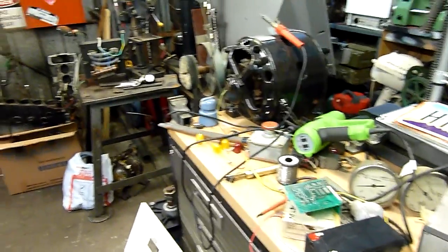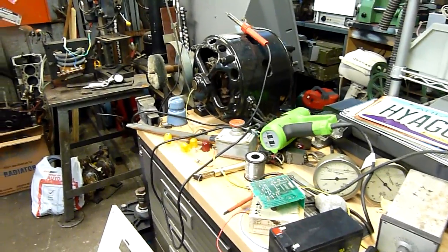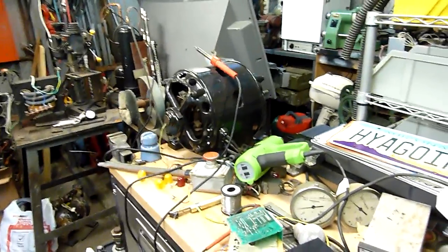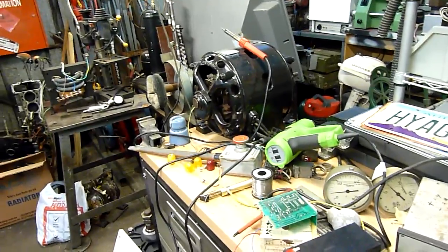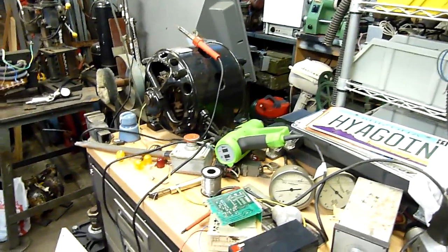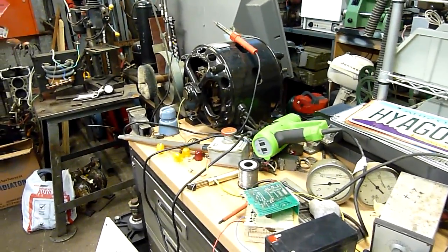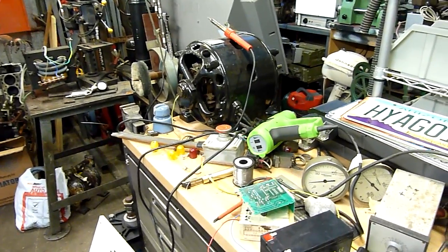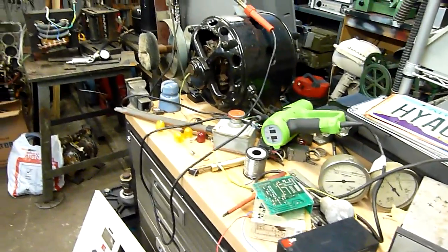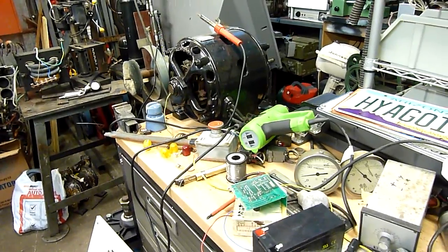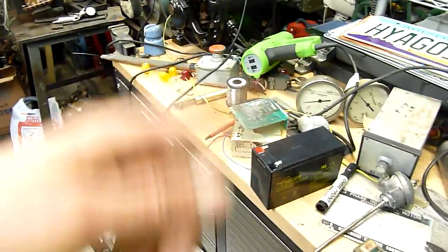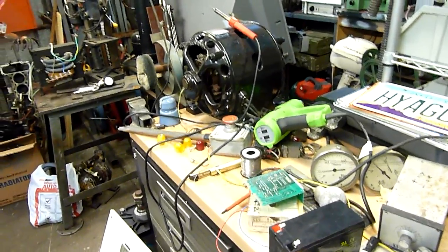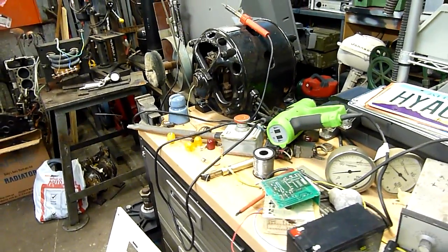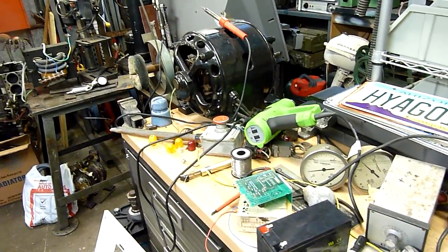Main thing I'm concerned about is this motor is oil cooled, or has an oil to water heat exchanger and everything in it. Likewise, I think a lot of that oil is also lube oil for the bearings, but I'm curious whether it would contain polychlorinated biphenyl. I doubt it, since it shouldn't be in contact with the windings. It wouldn't be inside the stator pack, because that would cause all sorts of problems at 2800 RPM. But I'm just curious as to the best way to test it.